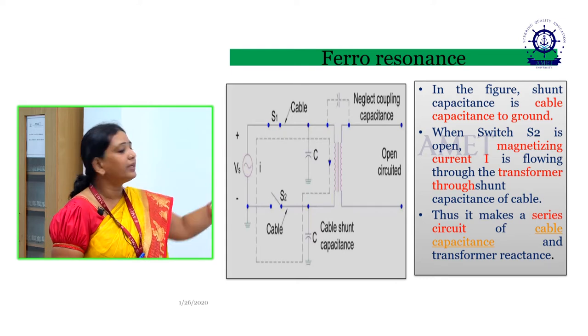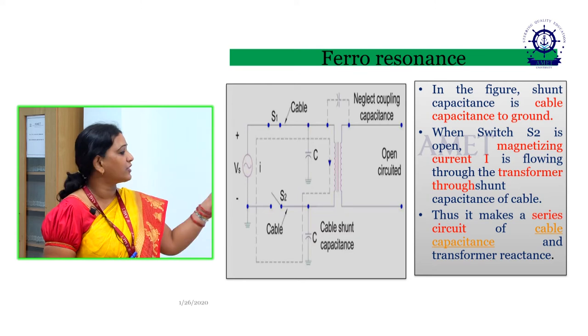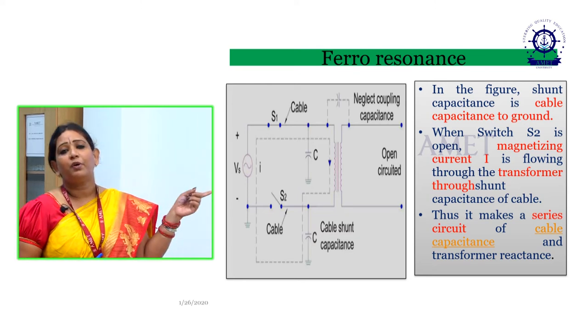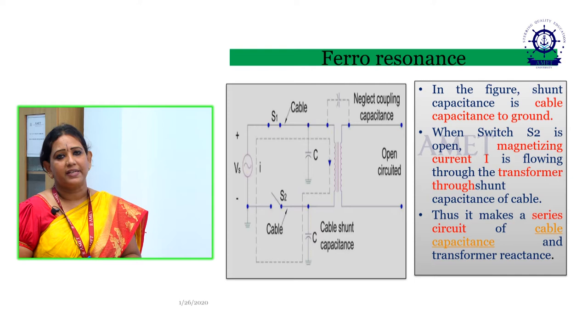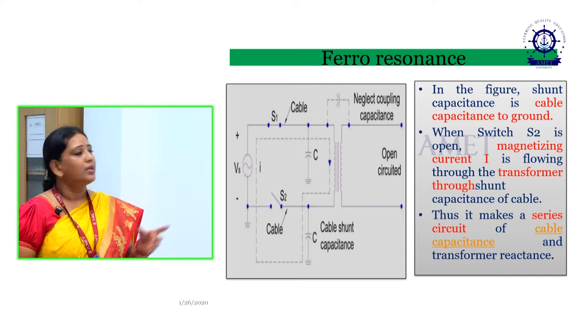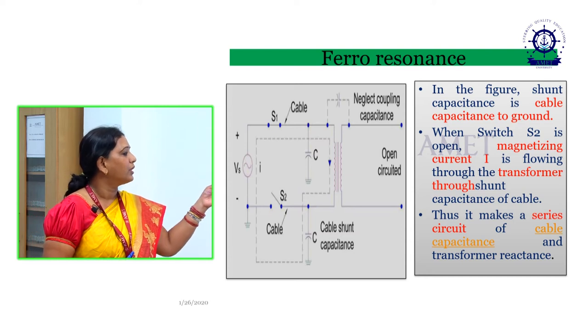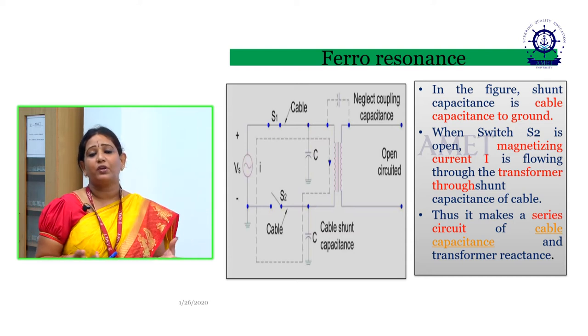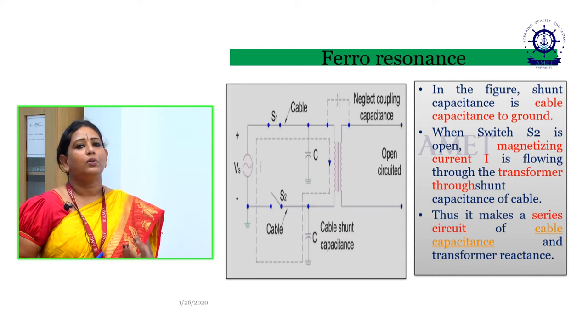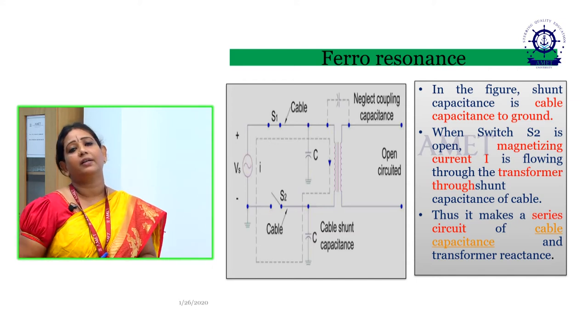So now the inductor and the capacitance, that is the shunt capacitance and the transformer inductance, both come in series, so that it creates a resonance phenomenon. Due to this combination circuit, these charges, because charge everyone knows is a current, inject a current into the system when S2 is open.